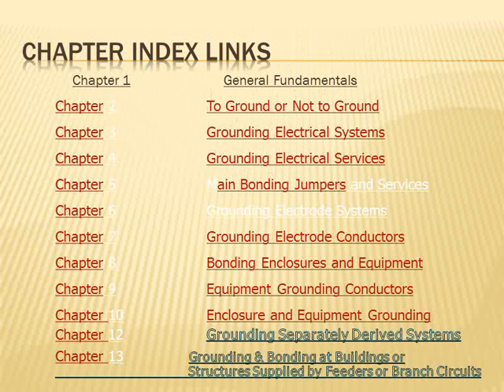That grounding electrode system only grounds anything metallic in your building. All the switch gear, the switchboards, the panels, the transformers that you want to operate. So the equipment must be grounded regardless if the system is grounded or not. That's what confuses people all the time. There's a difference between grounding the equipment and grounding the system.